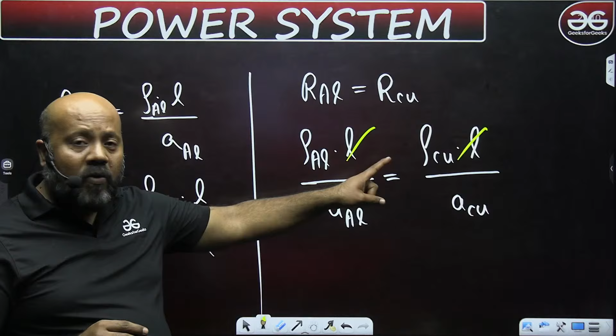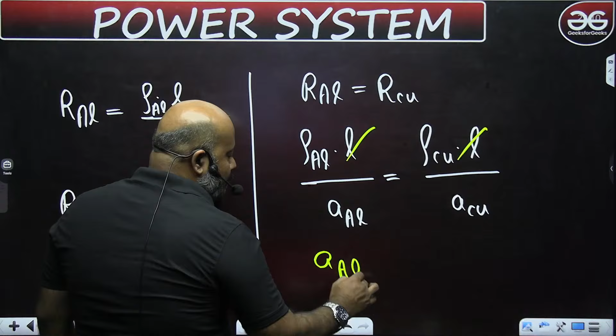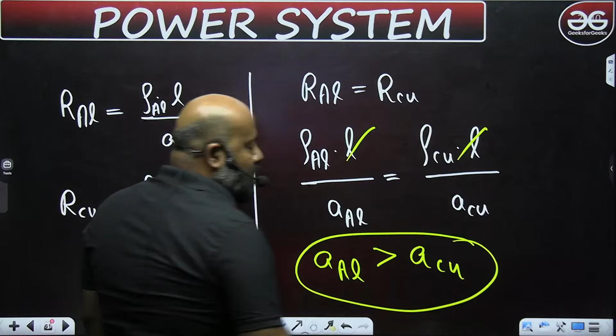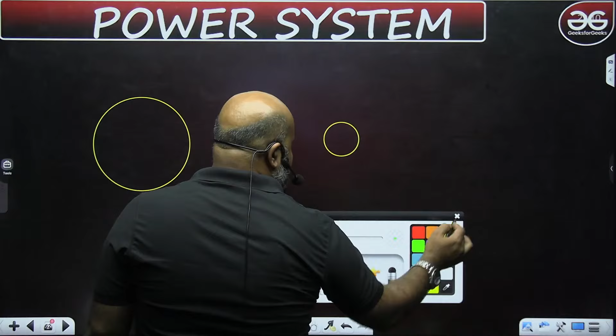Now, the resistivity of aluminium is higher than the resistivity of copper. So this condition can only hold if the cross sectional area of the aluminium conductor is more than the cross sectional area of the copper conductor. Say yes or no. It means your conductors are going to look something like this: this is your aluminium conductor and this is your copper conductor.